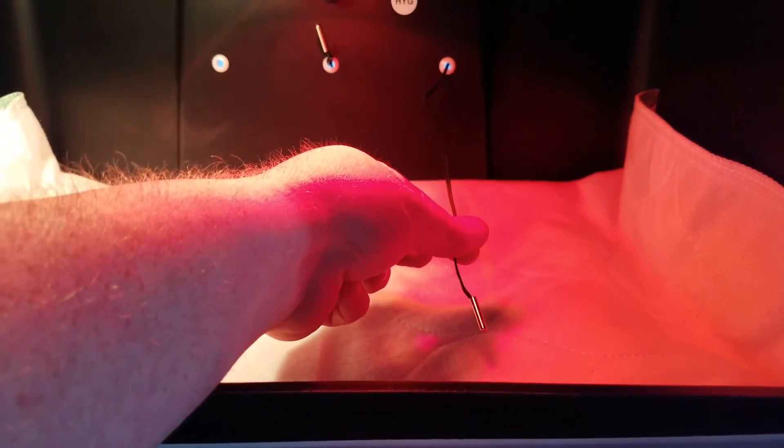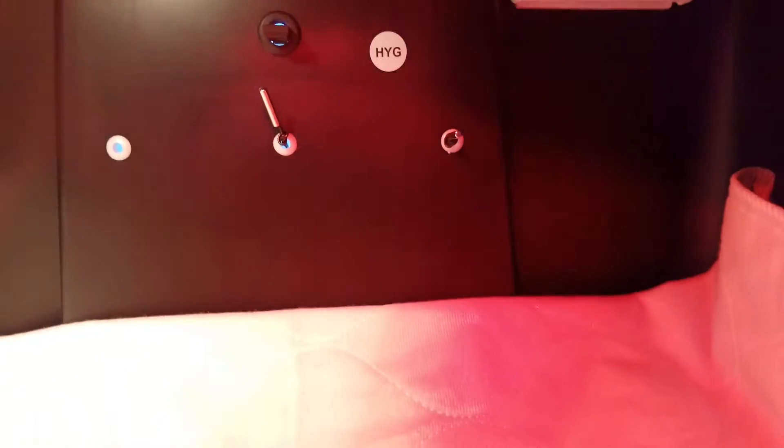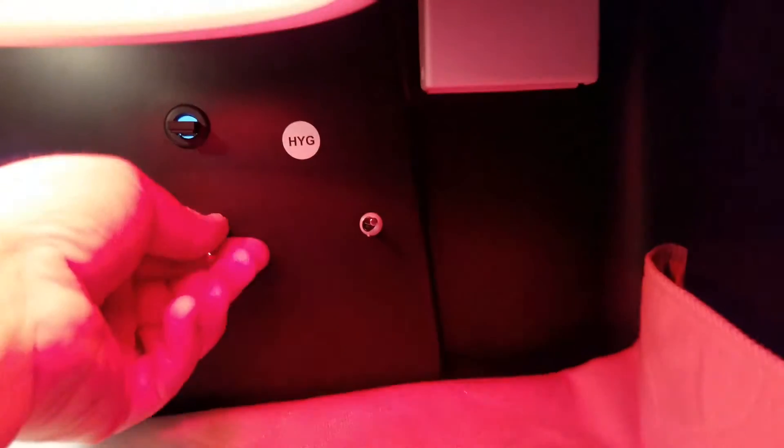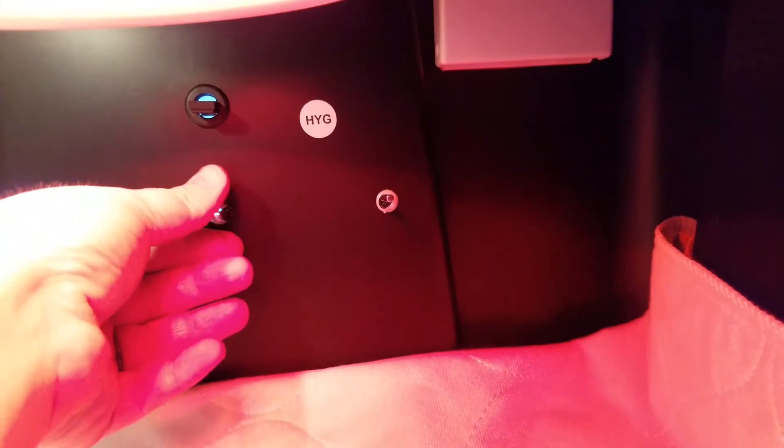Okay, so I've put a small loop in the sensor there, and now I'm just going to feed that back through. You can pull it through from the back side. I'm just going to feed that back through here so that now that sensor is sticking in and it isn't touching the wall there. It's just reading humidity here.